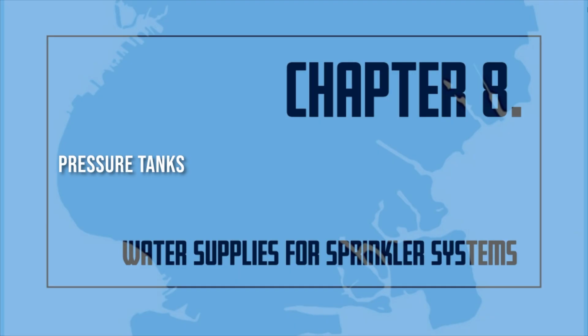Pressure tanks. Pressure tanks have several possible uses in automatic sprinkler fire protection systems. The tank is normally kept at 2/3 full of water and 1/3 full of air. The air pressure in the tank shall be maintained at or above 75 psi. Air for pressure tanks is supplied by air compressors.